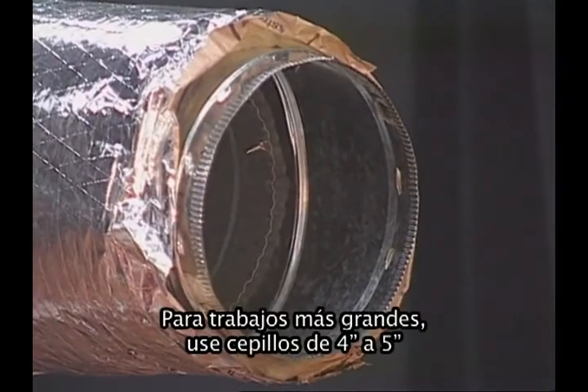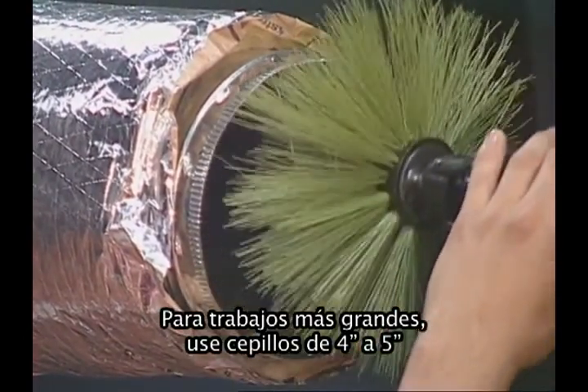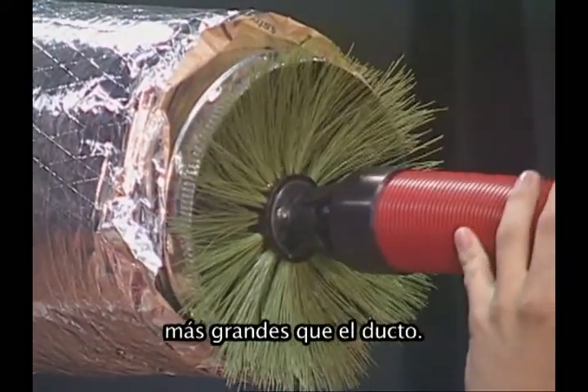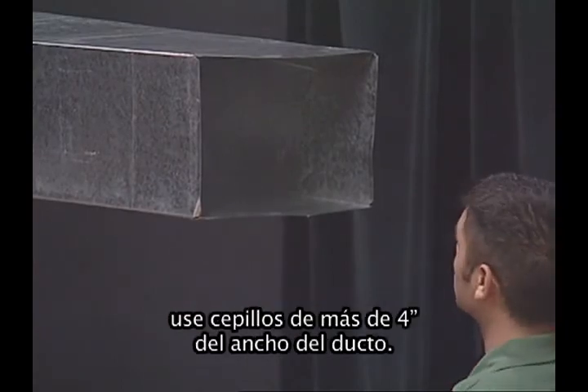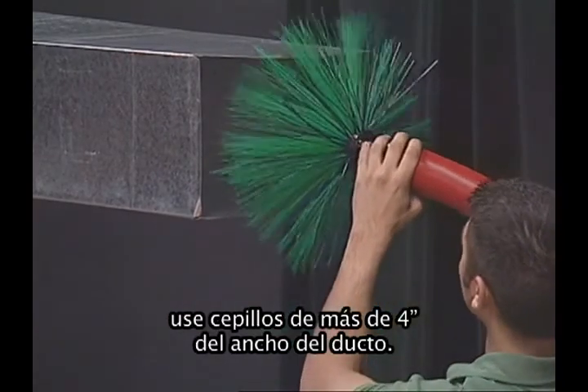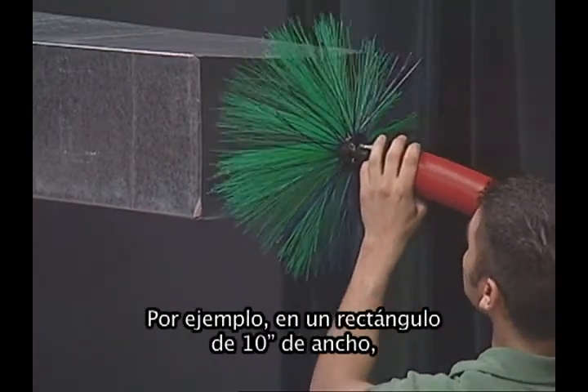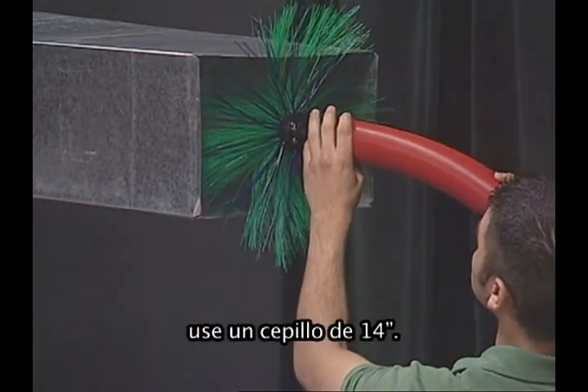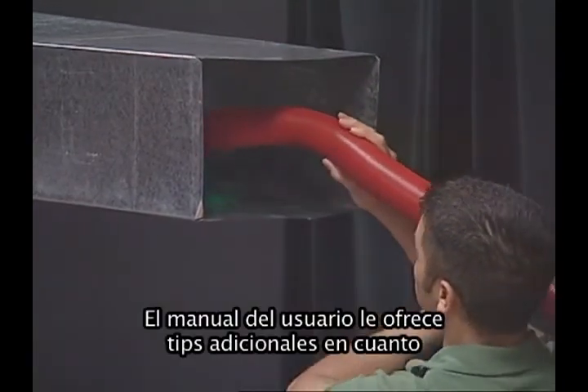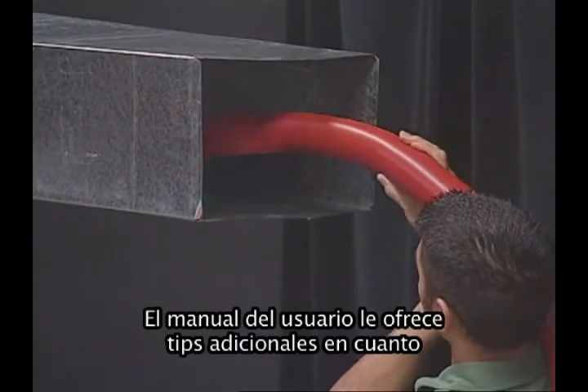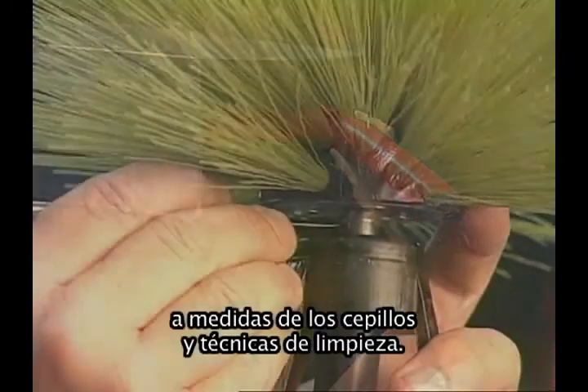For larger ductwork, use a brush 2 to 4 inches larger than the height of the duct. When cleaning rectangular ducts, use a brush 4 inches larger than the height of the duct. For example, in a 10-inch high rectangular duct, use a 14-inch brush. Your owner's manual provides additional tips on brush sizes and cleaning techniques.